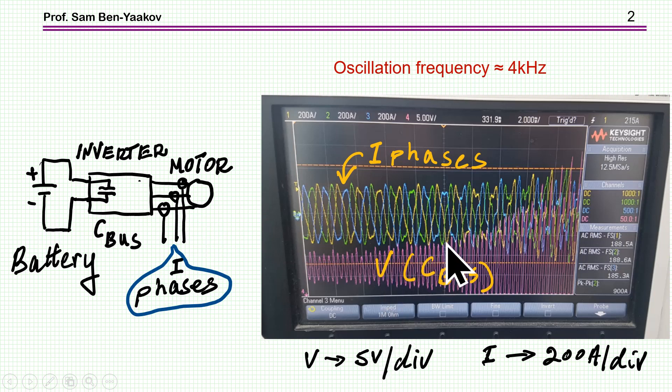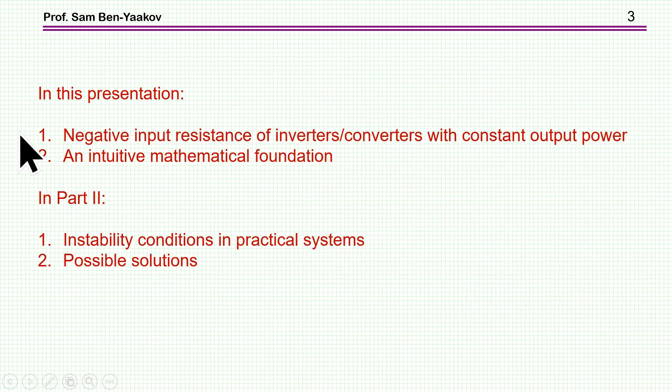Lo and behold, see how these oscillations are running away. There is actually an instability here, clearly, and if not stopped here, it would have caused a failure. So this is a real problem that we are now facing in the industry, and I'm going to discuss it to see what are the reasons and how to correct and remedy the problem.